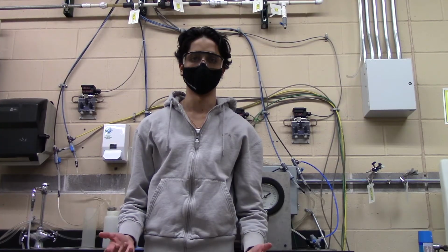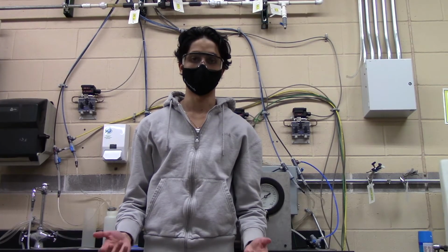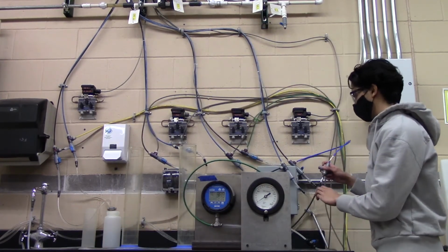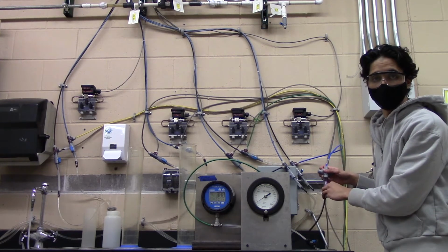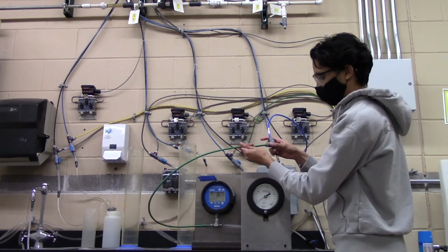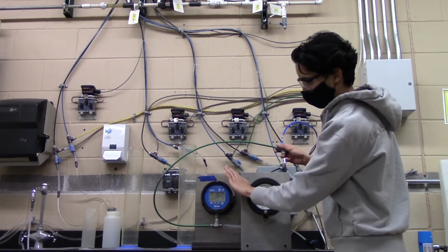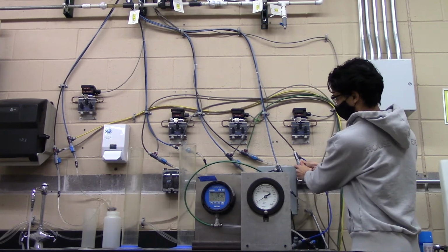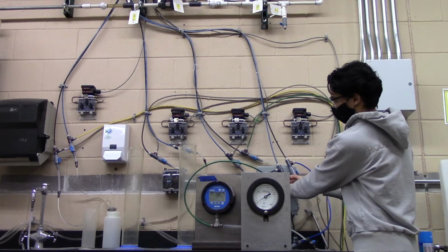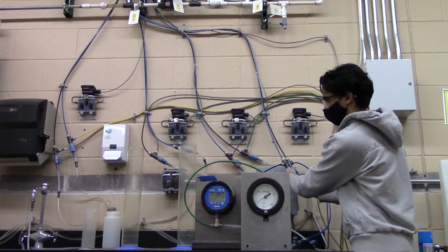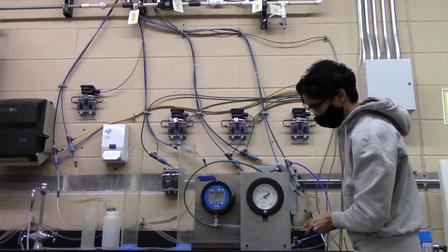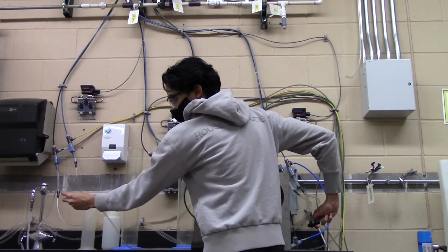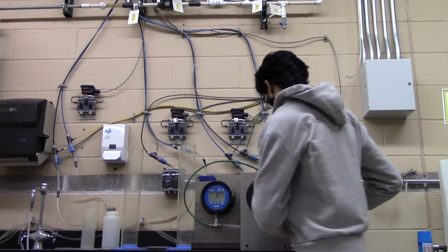Once you have set up your system to your desired flow rate, you may now take your pressure readings. To do so, you must find the three-way valve associated with whichever material you are working with. You then must connect this three-way valve to the pressure gauge. In order to remove any excess air out of the system, you must bleed out your material's valve for at least 30 seconds. Once you are done bleeding and your valves are closed once more, you must bleed out the pressure gauge's valve again for 30 seconds.